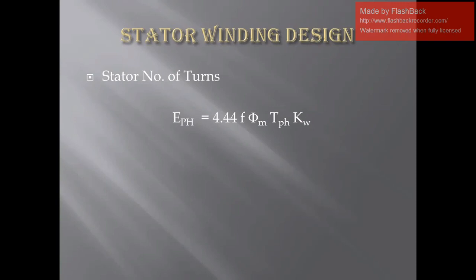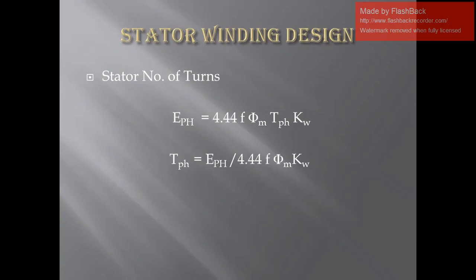To calculate stator number of turns, we use the induced EMF per phase equation: E = 4.44 × f × Φ_max × T_s × k_w, where f is frequency, Φ_max is maximum flux, T_s is number of turns per phase, and k_w is the stator winding factor. If all quantities are known, we can easily calculate stator number of turns per phase. The flux Φ is the maximum flux, and from the specific magnetic loading — which is already available — we can easily calculate our flux Φ.